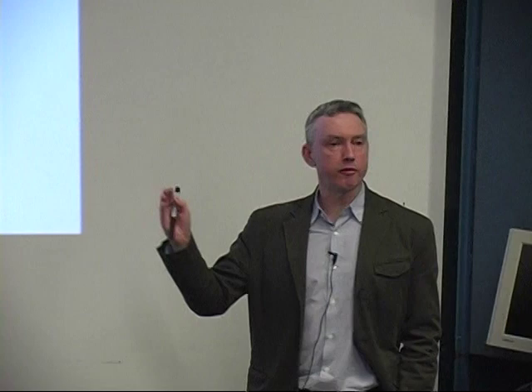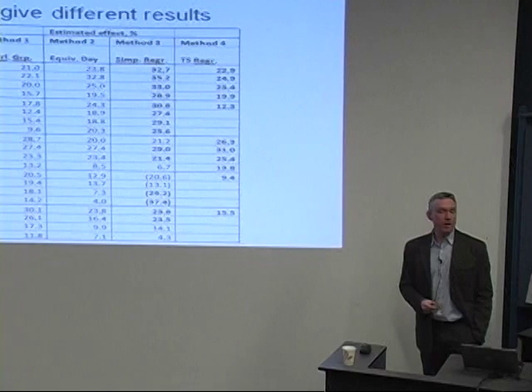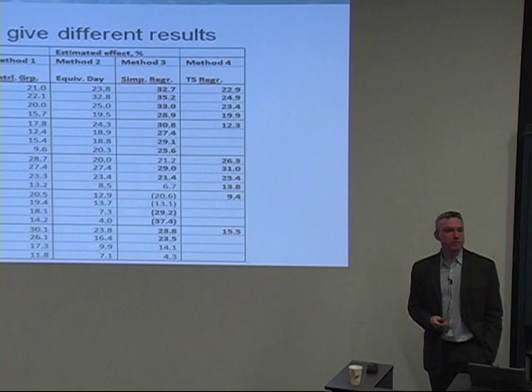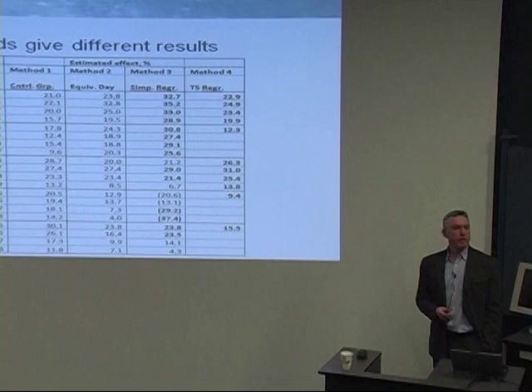When you increase the thermostat by two degrees, the air conditioner immediately goes off and you save some power. But as the house warms up and hits the new thermostat set point — two degrees higher — the air conditioners come back on, so savings tend to decline over the four-hour period. Another important thing to notice is that the different techniques differ in their estimates of effect size by a factor of 50% to 200%, which matters significantly if a utility is designing an incentive program.